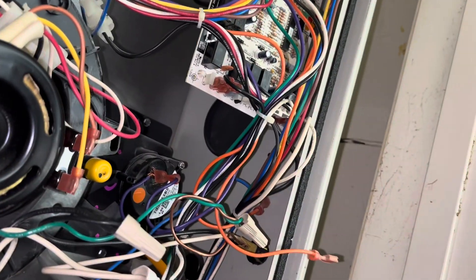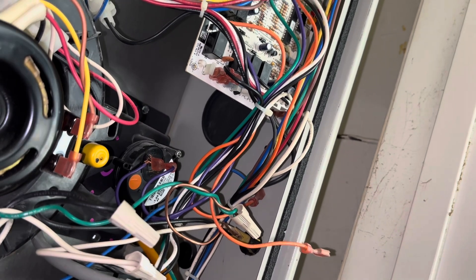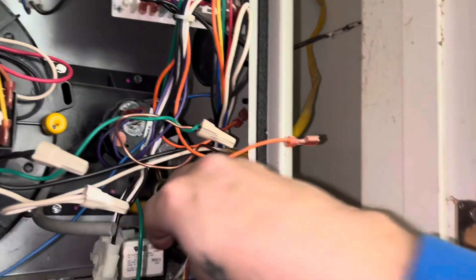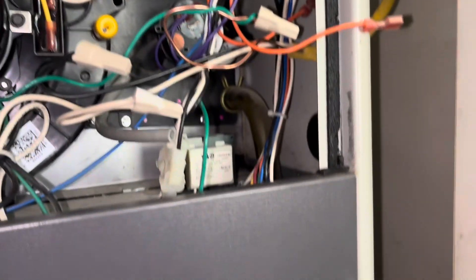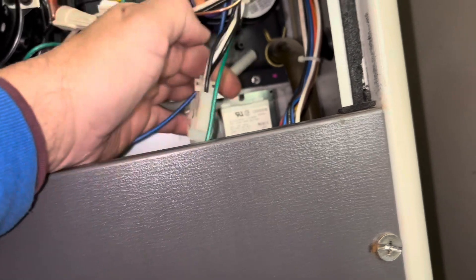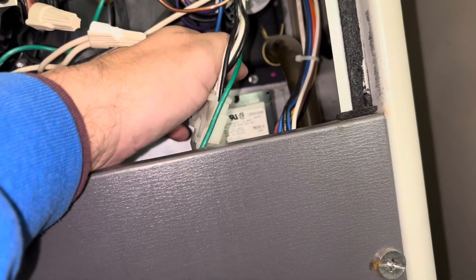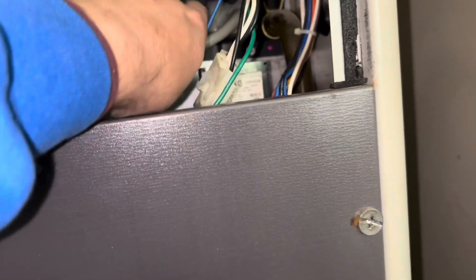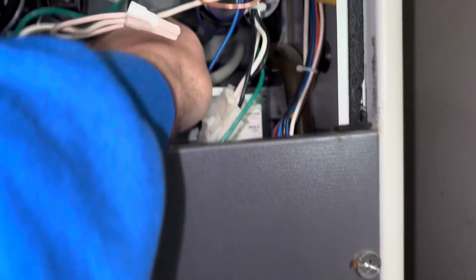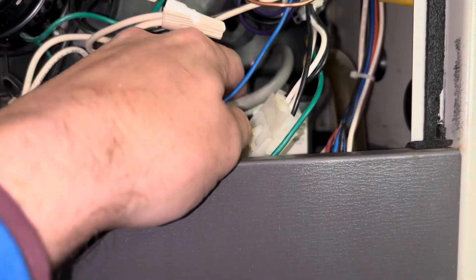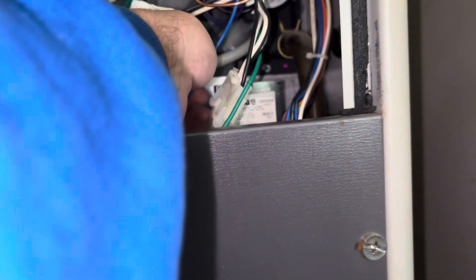So I'm just going to hook up this orange piece of hose right here, and I'm just going to blow through it and make sure it's good and cleared out. So in a minute here, I'm going to fire it back up and make sure we're good to go. The gray tube right there actually goes to the pressure switch. So I'm not a huge fan of this furnace just because of how cheaply made it is. It's a very budget two-stage furnace, but they do work. I do not expect this furnace to last 20 years just because of how cheaply made everything is on it. I've already done two or three heat exchangers in this complex for these style furnaces.